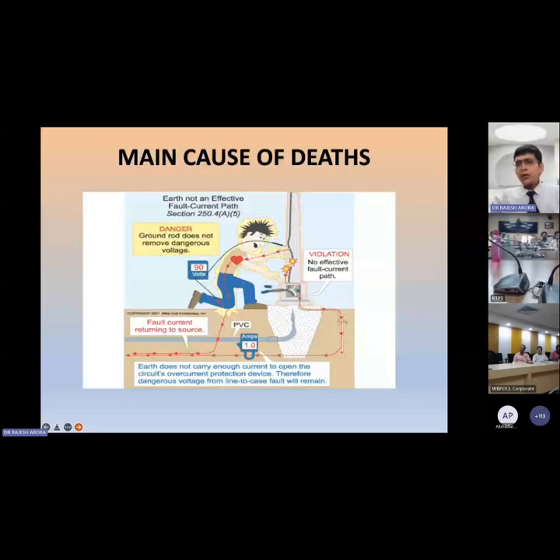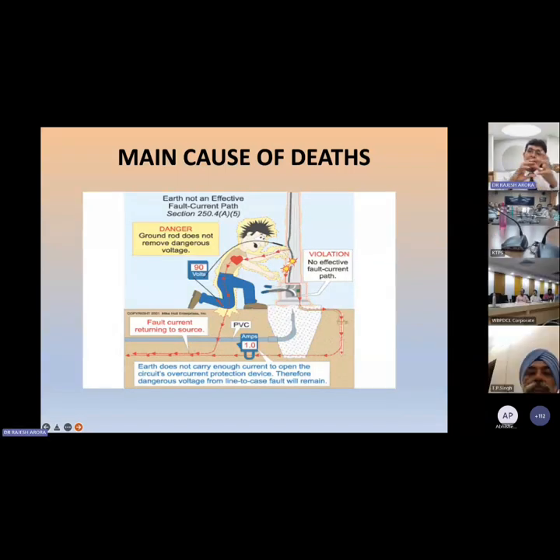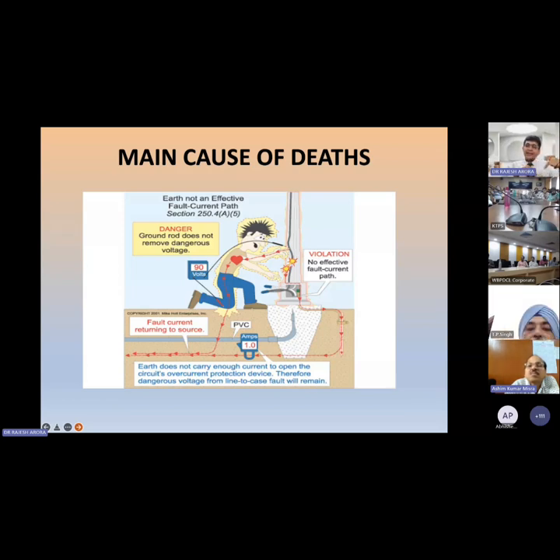I started my presentation with the electrocution of people touching the pole. But try to understand why it is happening. It is happening because, despite earthing of that pole, the resistance of the path going back to the source is quite high. Because of that high resistance, there is what is called earth surface potential. Because of earth surface potential, there is a potential difference between your leg and the hand touching that pole. Because of that potential difference, current starts flowing and you get electrocuted. The main reason is the touch potential, especially in the monsoon season.